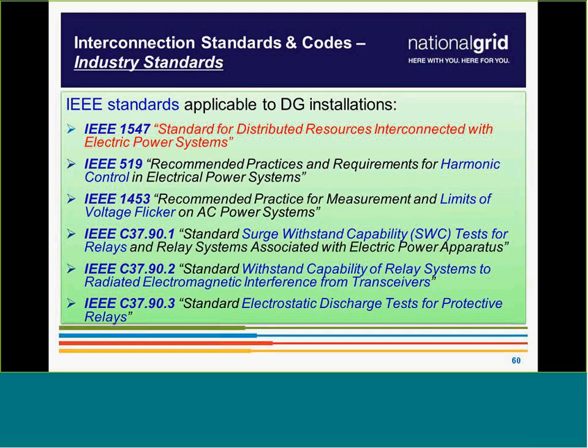In addition to IEEE 1547, you have IEEE 519 for harmonics, and 1453 for flicker, and then the C37.90 series. This is an important series of standards - if you just keep in your mind C37.90 and utility grade, we're all set.